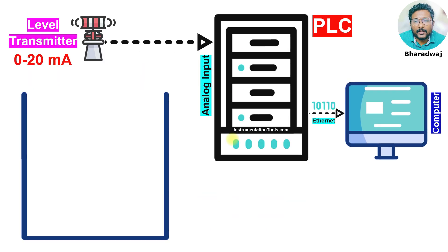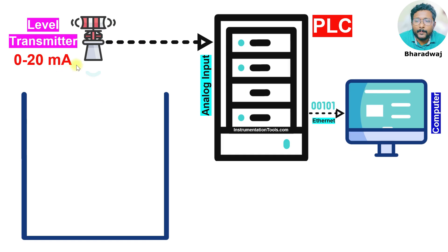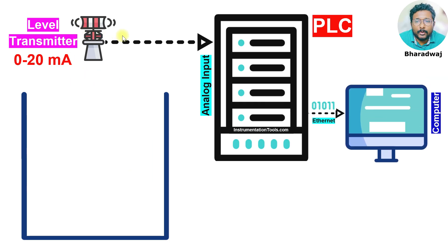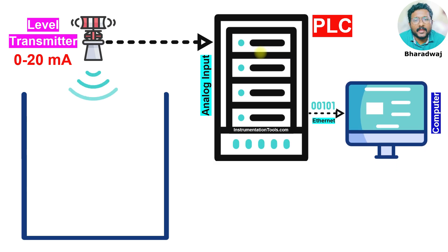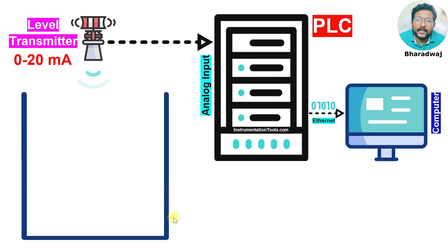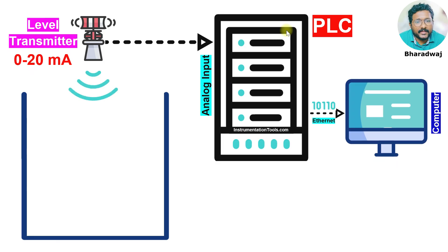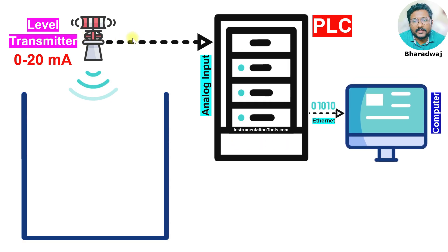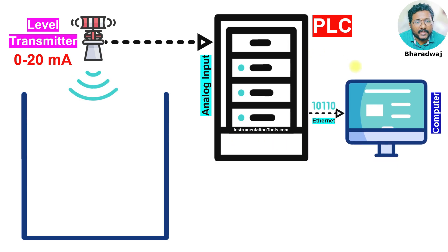I will go to the same example. We have a tank and there is a level transmitter which measures the tank level. This transmitter range is 0 to 20 mA. When the tank level is 0%, the transmitter sends 0 mA to the PLC. If the tank is full, the transmitter sends 20 mA to the PLC. If the tank is 50%, the transmitter sends 10 mA to the PLC, and the PLC calculates the equivalent tank level and displays it on the computer.